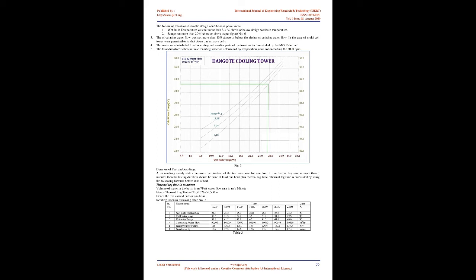In operational performance assessment, the typical measurements and observations involved are: 1. Cooling tower design data and curves to be referred to as the basis. 2. Intake air WBT and DBT at each cell at ground level using a whirling psychrometer. 3. Exhaust air WBT and DBT at each cell using a whirling psychrometer. 4. CW inlet temperature at risers or top of tower, using accurate mercury in glass or a digital thermometer.